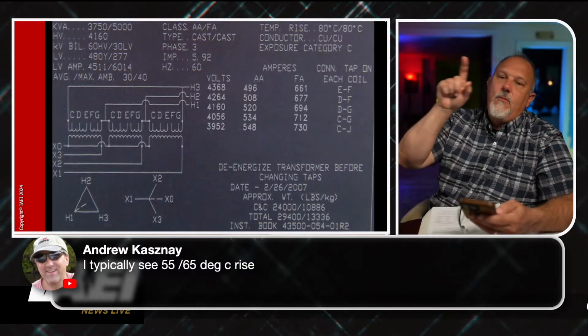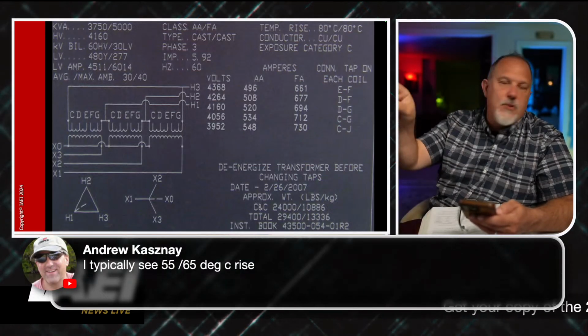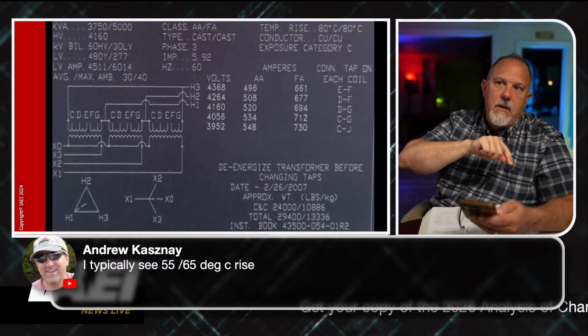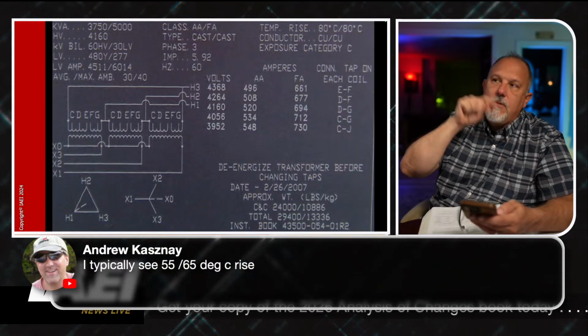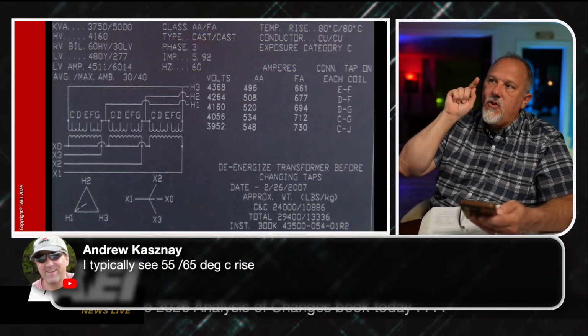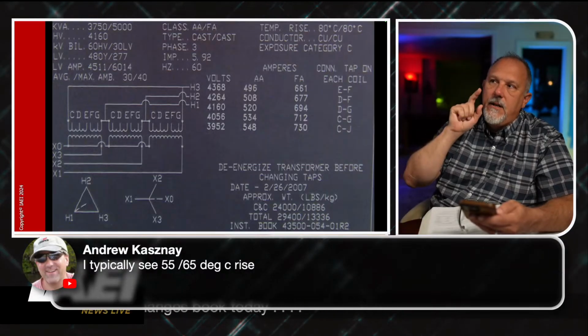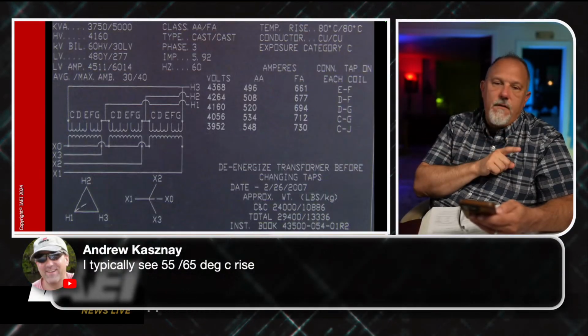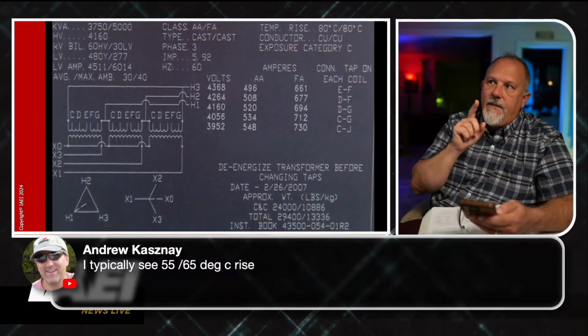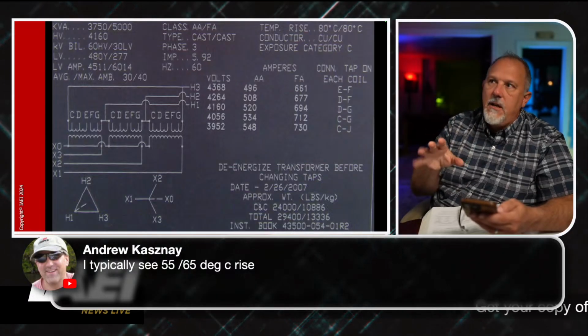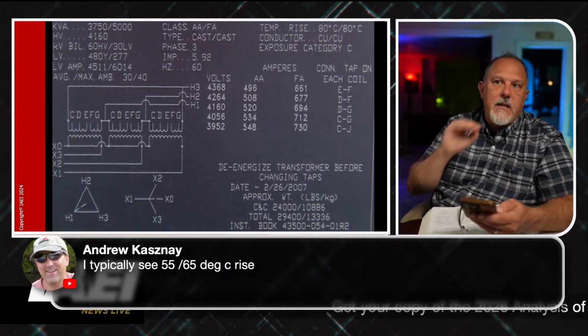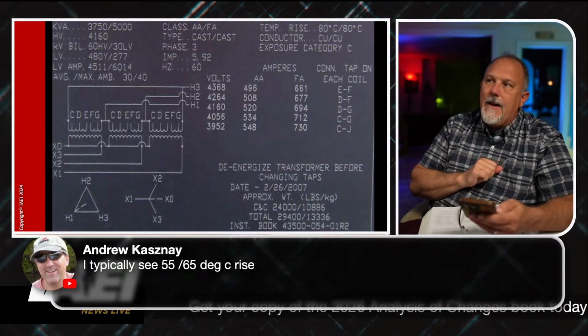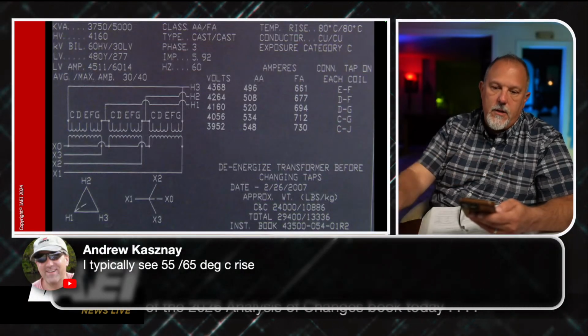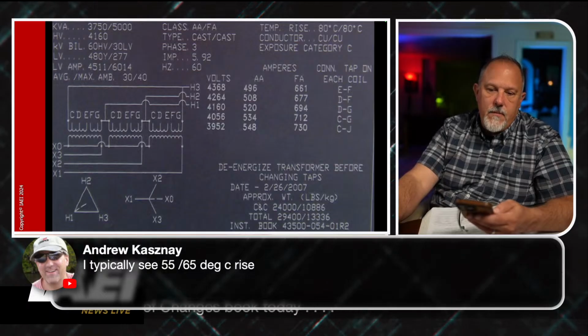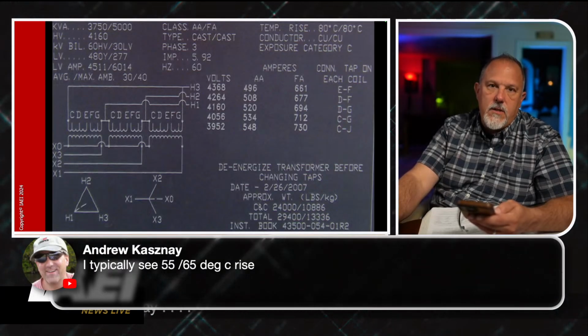But I'm not sure of the relationship between that temperature rise and the insulation. I think the insulation of your conductor has to be greater than the temperature rise of the transformer itself. And if I'm using 90 degrees C insulation, then I don't have to worry about it because I'm not exceeding the 90 degrees C insulation. But I need to do a little bit more homework on that question, Andrew. Leave it to you to stump me.